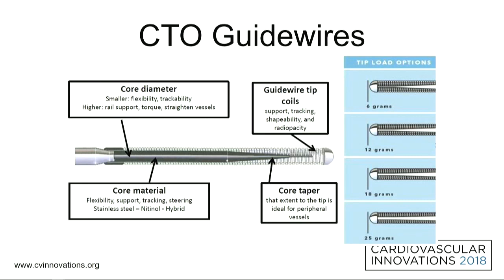I could give an hour lecture on the engineering of guide wires — it's such a complex and important process. Just to give a very short description: it's all about the core diameter and core material. The vast majority are made of stainless steel; the core diameter is usually 0.035, 0.018, or 0.014 inch. The tip is very important — in engineering terms, this is about the relationship between the grind and the taper. The coils coat the outer lining of the tip and can either be bare coils or coated in a polymer jacket, which gives lubricity and tactile feedback.